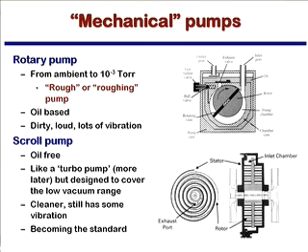Also, the mechanism that they're using can introduce vibration. So in the microscopy world, if you use one of these things and you have a fairly high resolution microscope, this thing will sit quite some distance away, preferably on a different piece of concrete slab than your microscope. And so this is something to be concerned with.